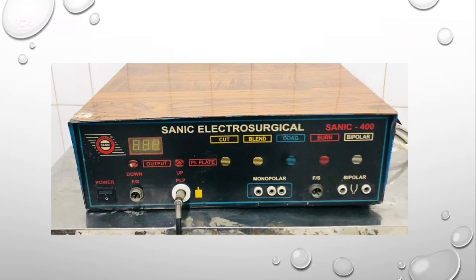This is a typical electrosurgical unit used in surgeries for cutting and coagulating tissues with electrical current. The power switch turns the machine on and off. Up and down buttons increase or decrease power. The plate light shows if the patient plate is connected. There are different modes in these electrosurgical units: cut for cutting tissues, blend, a mix of cutting and coagulation, coagulation for stopping bleeding, burn for burning or sealing, bipolar for bipolar instruments, monopolar for monopolar tools, and FS for foot switch control.